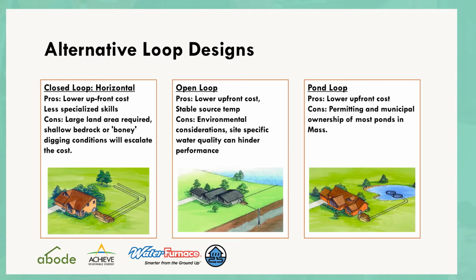In Massachusetts, the permitting is just crazy to try to do this for two reasons. One is Conservation Commission permitting, so you're not just digging in the buffer zone, you're actually digging into the pond. Because we transition to the pond, the piping has to be below frost line. And in Massachusetts, people typically don't own the pond, they own up to the frontage, and the pond's owned by the municipality, so now you're asking to put your ground source under some public body of water. And so it's just not so commonly done. More common in New Hampshire, it's based on local state regulations.